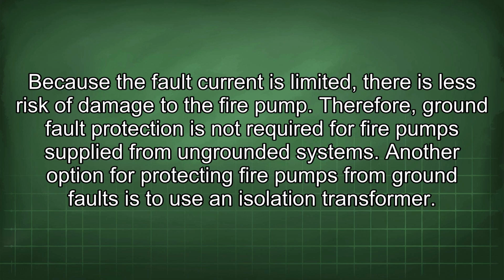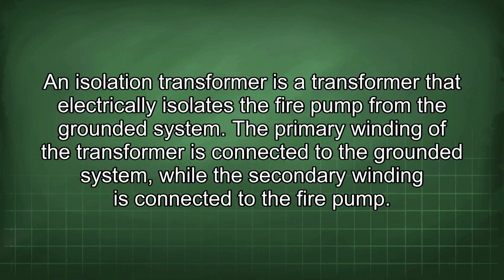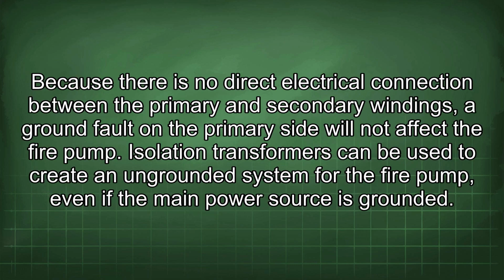Another option for protecting fire pumps from ground faults is to use an isolation transformer. An isolation transformer is a transformer that electrically isolates the fire pump from the grounded system. The primary winding of the transformer is connected to the grounded system, while the secondary winding is connected to the fire pump. Because there is no direct electrical connection between the primary and secondary windings, a ground fault on the primary side will not affect the fire pump.